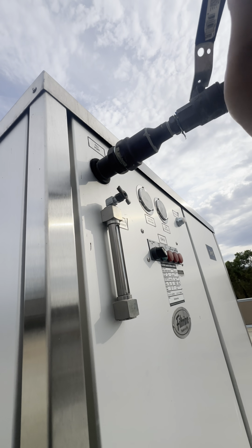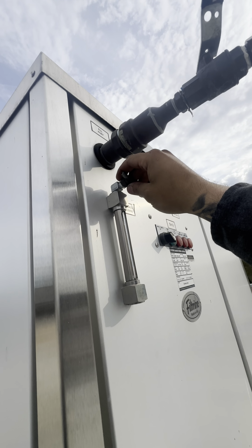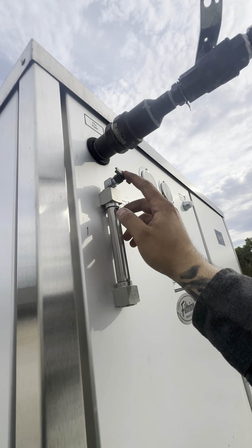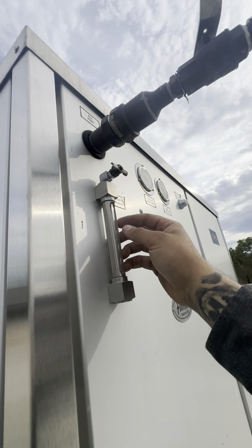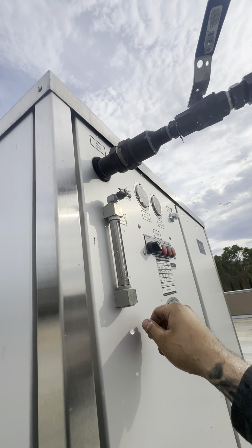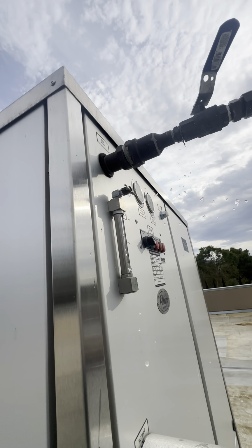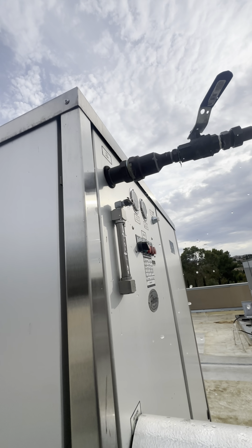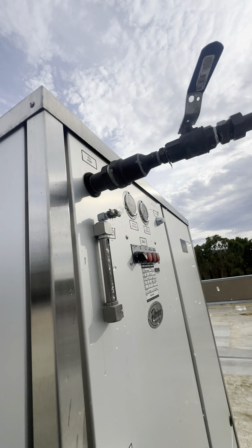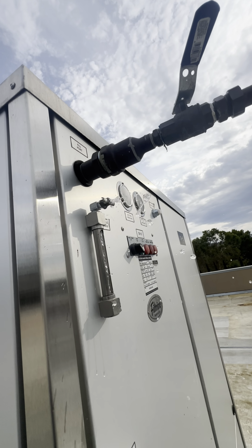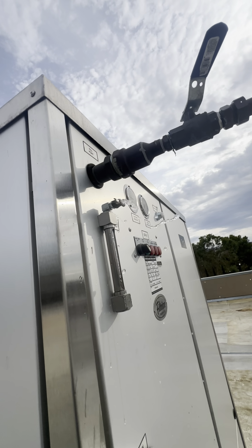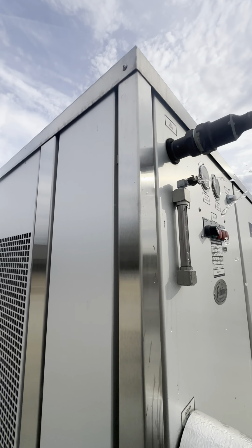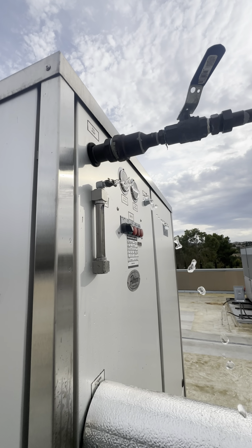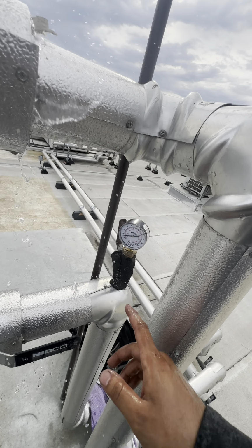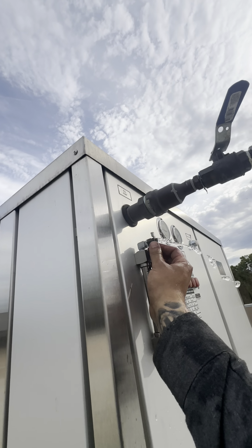We can open up the fill port, go ahead and crack this wing nut, and it'll fill the loop with water. If you want to bleed out the air, once we bleed out most of the air, then we can cycle the pump on and go from there just to start the chiller. Once you get a little clean geyser without air bubbles, we do have some pressure inside the gauges now. You can go ahead and close that.